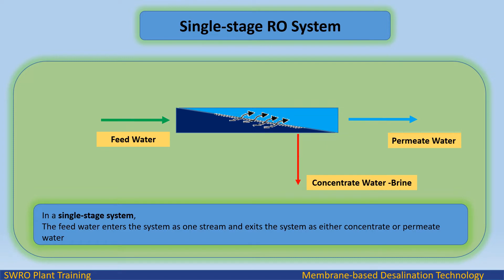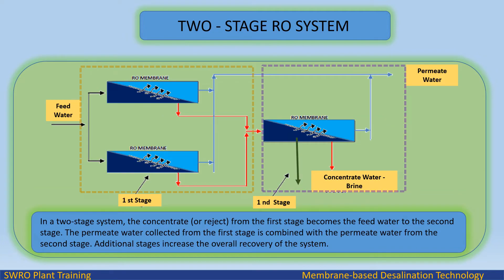In a single stage RO system, the feed water enters the system as one stream and exits the system as either concentrate or permeate water. In a 2 stage system, the concentrate or reject from the first stage becomes the feed water to the second stage. The permeate water collected from the first stage is combined with the permeate water from the second stage. Additional stages increase the overall recovery of the system.